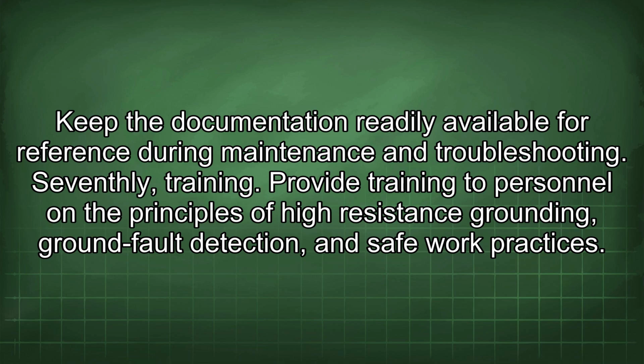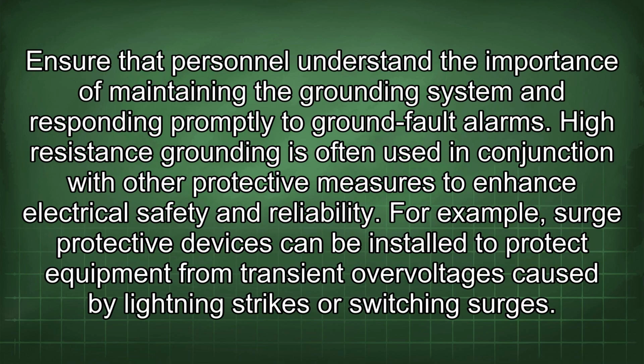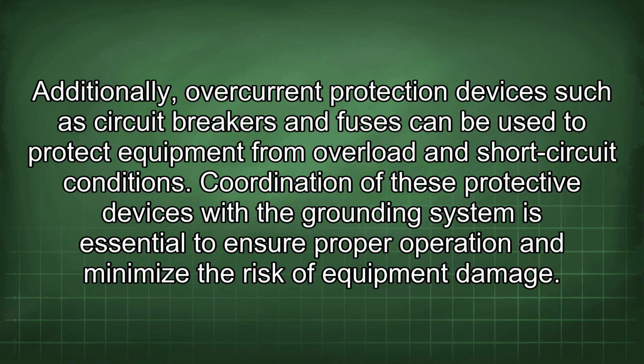Seventhly, training. Provide training to personnel on the principles of high-resistance grounding, ground fault detection, and safe work practices. Ensure that personnel understand the importance of maintaining the grounding system and responding promptly to ground fault alarms. High-resistance grounding is often used in conjunction with other protective measures to enhance electrical safety and reliability. For example, surge protective devices can be installed to protect equipment from transient overvoltages caused by lightning strikes or switching surges. Additionally, overcurrent protection devices such as circuit breakers and fuses can be used to protect equipment from overload and short-circuit conditions.